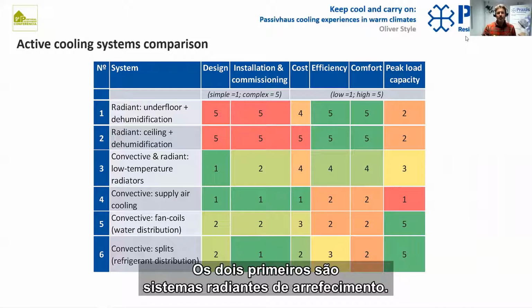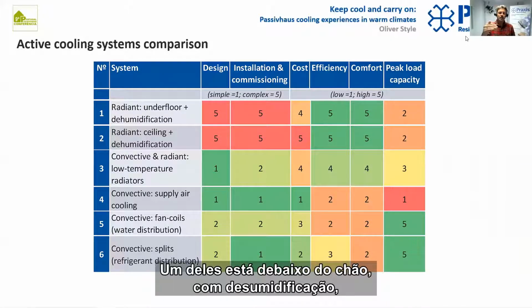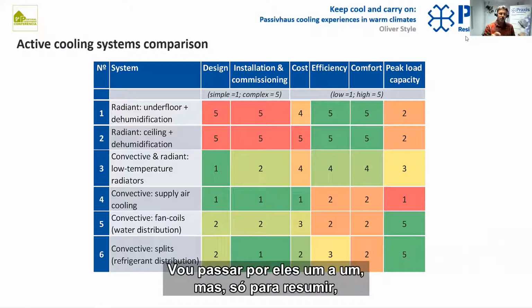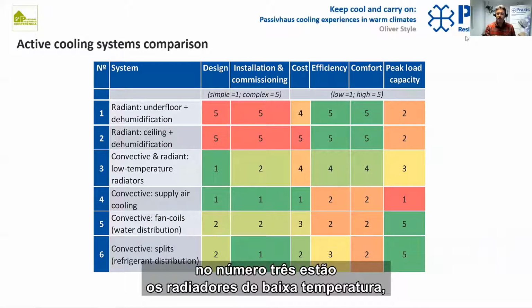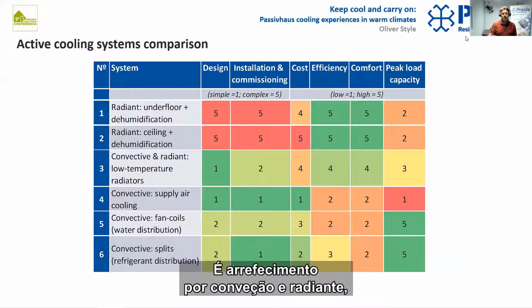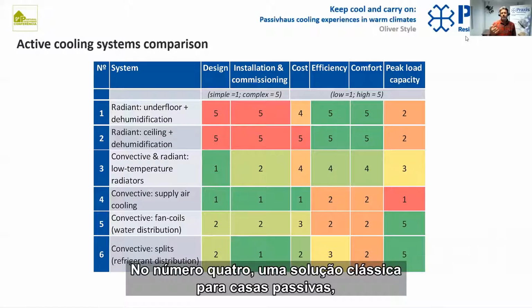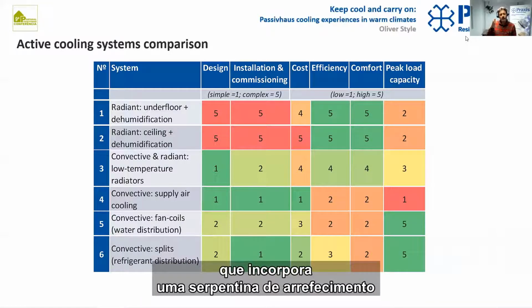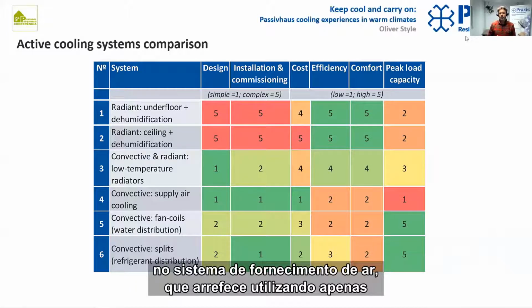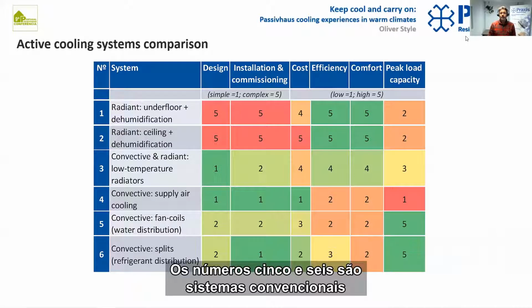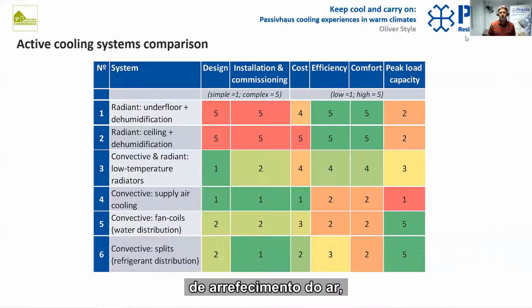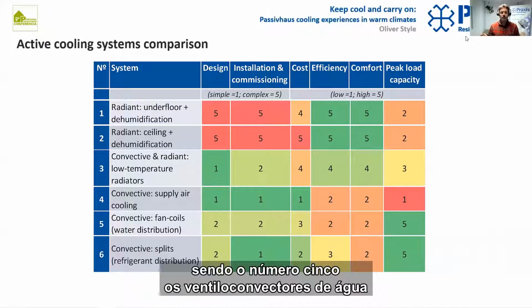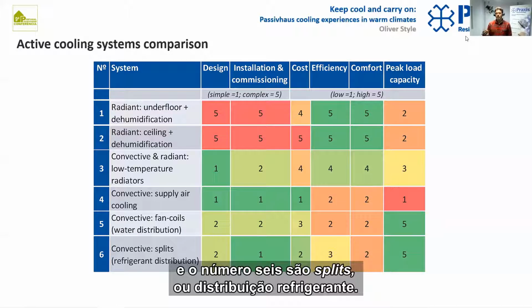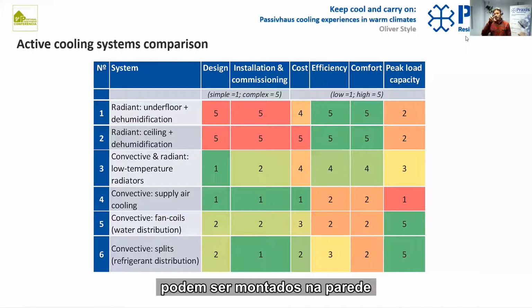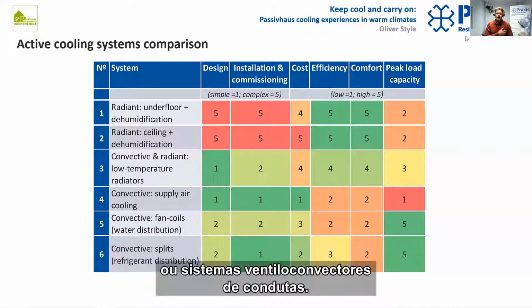So the first 2 systems are radiant cooling systems. One is underfloor with dehumidification, and then the other, number 2, is radiant ceiling with dehumidification. Okay, I'm going to run through each one by one, but just to summarize them. Number 3, low temperature radiators, basically floor mounted fan coils, which is both convective and radiant cooling. And number 4 is a classic passive house solution of incorporating a cooling coil on the supply air stream and just cooling using the ventilation supply air. 5 and 6 are conventional air cooling systems, 5 being fan-coils, i.e. water distribution, and 6 being splits or a refrigerant distribution. In both cases, those can be either wall-mounted or ducted fan-coil or split systems.